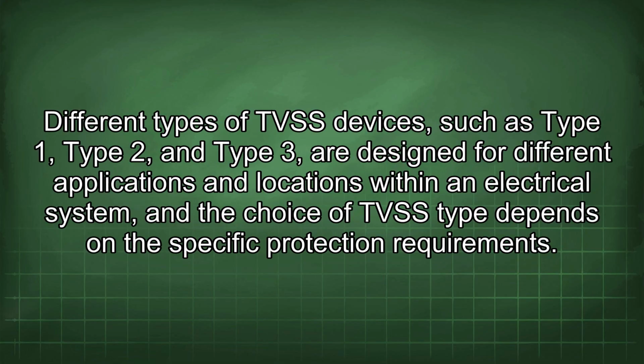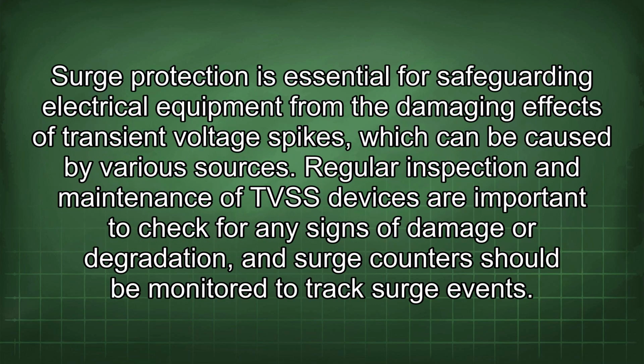Different types of TVSS devices, such as Type 1, Type 2, and Type 3, are designed for different applications and locations within an electrical system, and the choice of TVSS type depends on the specific protection requirement. Surge protection is essential for safeguarding electrical equipment from the damaging effects of transient voltage spikes, which can be caused by various sources.